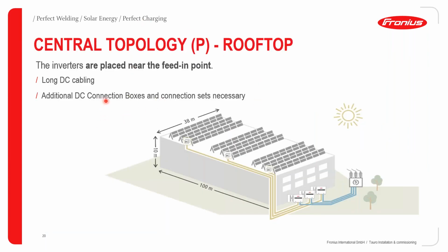Let's now look at the central topology, or what we call the P version. In this case, we are looking at an installation done on a rooftop. So all the inverters will be placed near each other in a central position. In this particular case, we are covering an average of about 110 meters from the farthest strings to where the inverters are positioned. And this is possible because the Tauro inverters can handle 95 millimeter square on the DC side strings.